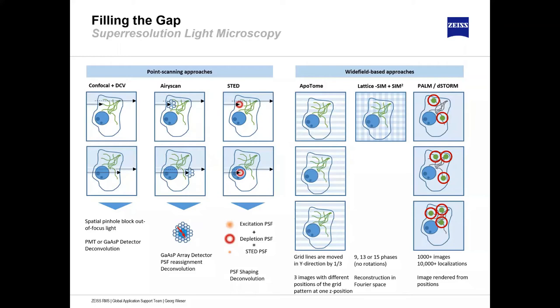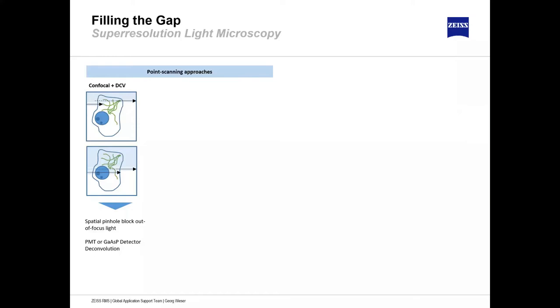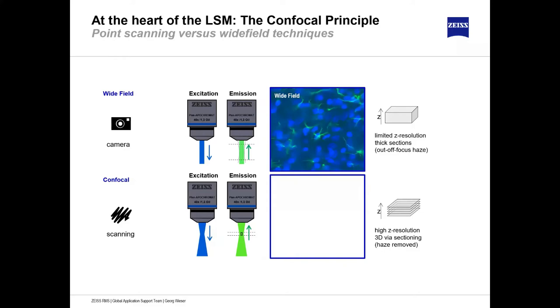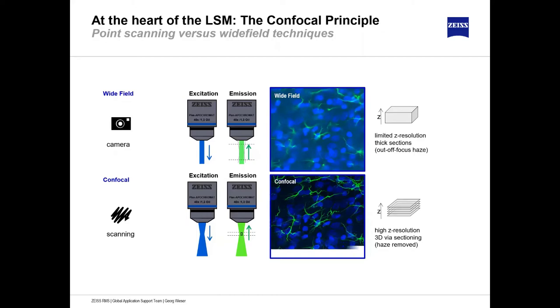We start with confocal combined with deconvolution. In wide field microscopy, the whole field of view is illuminated evenly and the emission light is captured with one camera snap — saving time, but with thicker samples the out-of-focus light blurs the image and reduces contrast and resolution. In confocal microscopy, only one focal point is illuminated at a time. You invest time to scan your sample, but you get contrast and good resolution.